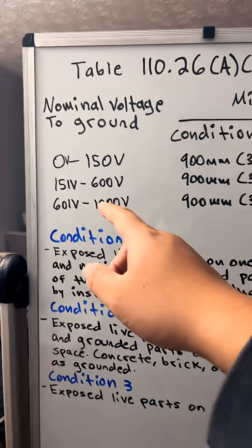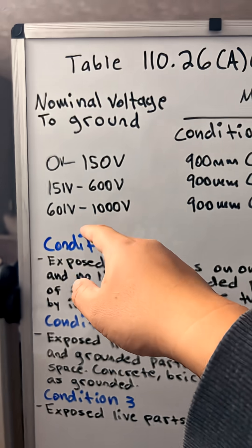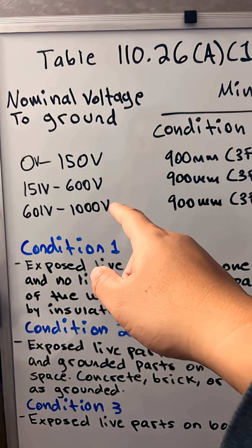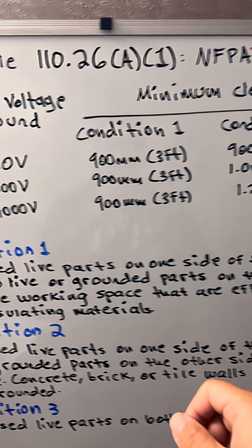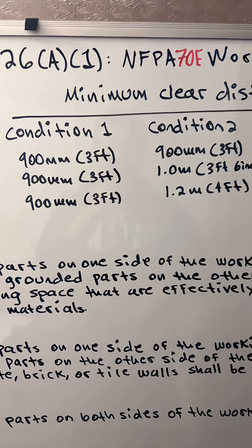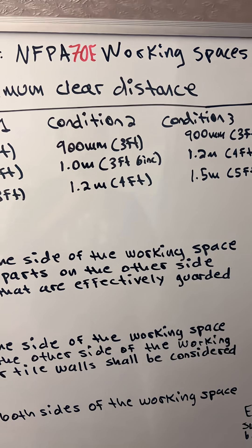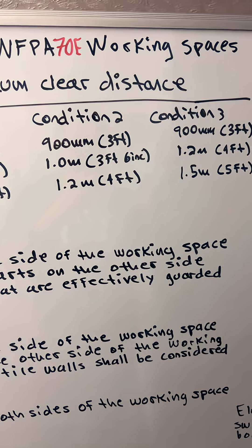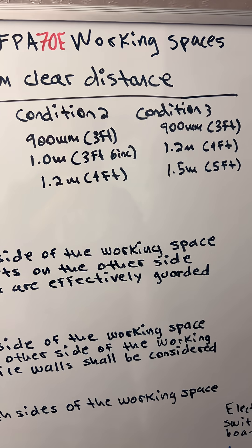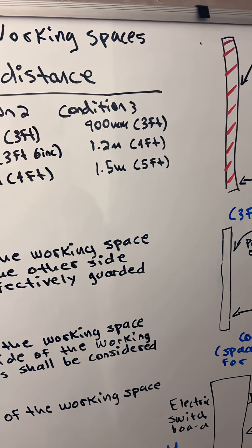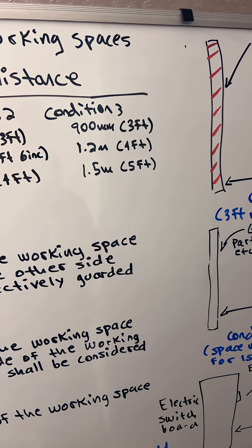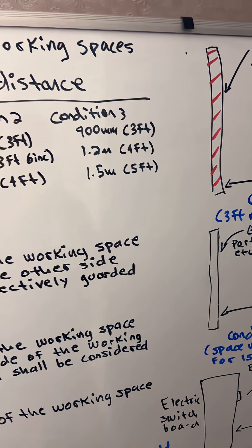From 151 volts to 600 volts: condition 1 is 3 feet, condition 2 is 1 meter or 3 feet 6 inches, and condition 3 is 1.2 meters or 4 feet.